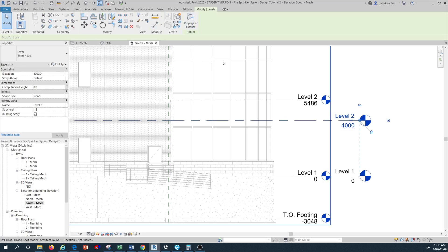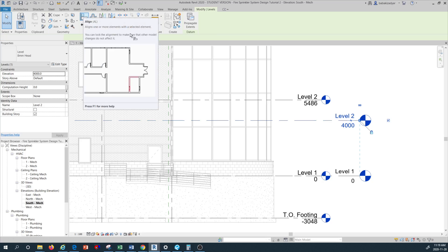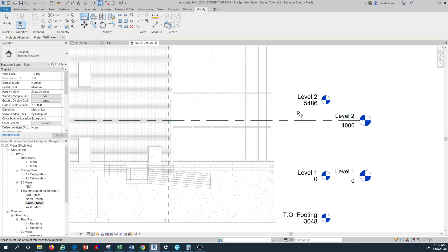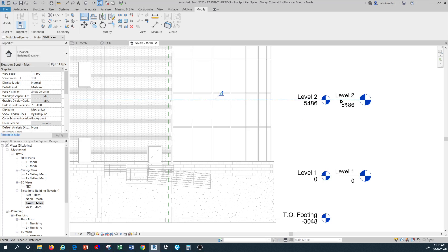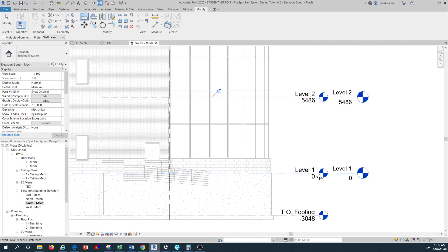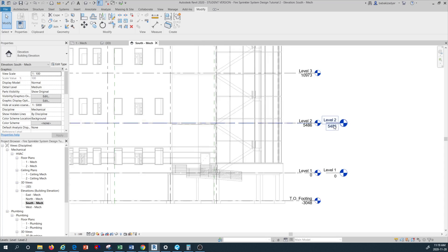I'm going to use the Align command. While highlighting this level, I can come here and use the Align command, or simply type AL. The command is applied and the cursor symbol changes. I'm going to select a destination level - the architectural level - and then select my mechanical or sprinkler model level. My model is going to be aligned with level two. Level one is already aligned, so I won't make changes there. I press Escape and now I have aligned the two levels.